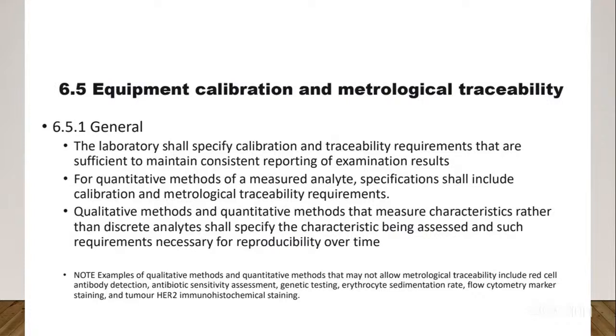Even for pipettes, you need to do the calibration of the pipette. You need to do the calibration of your centrifuge. You need to do the calibrations of most of the equipment we are using. And that is why it's important for us to calibrate our equipment. The calibration report for some is different, but for some equipment, you can't even use it without doing calibration. Like chemistry analyzers, you have to do the calibration. And if calibration fails, you cannot continue.